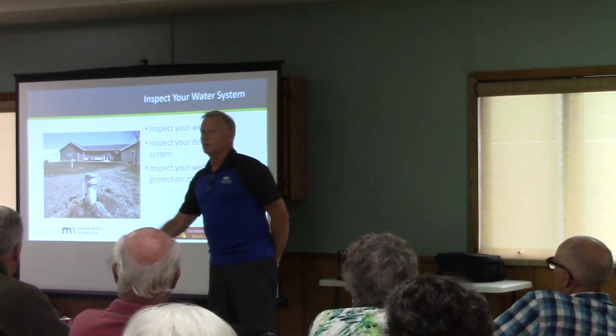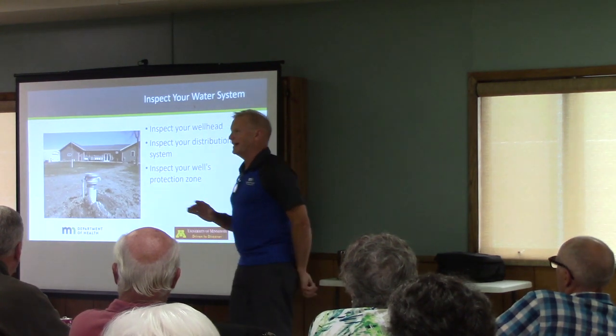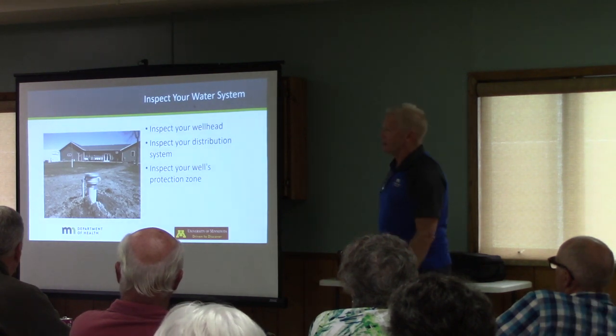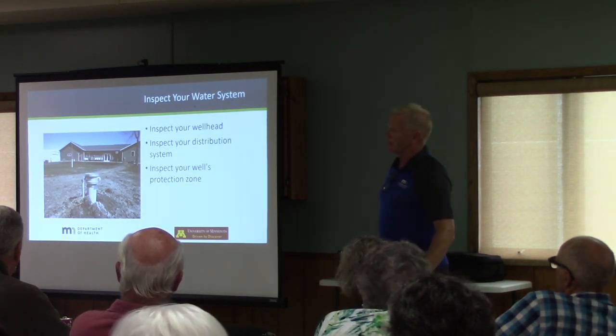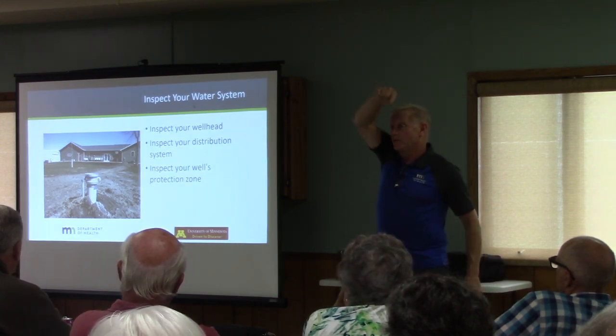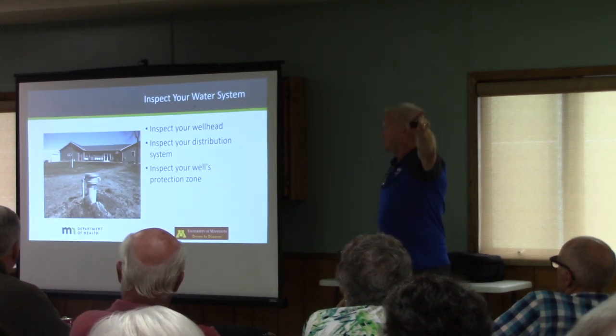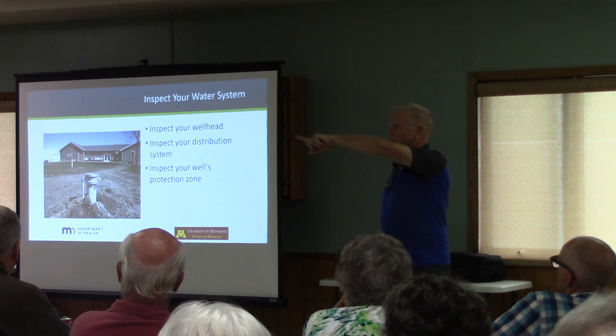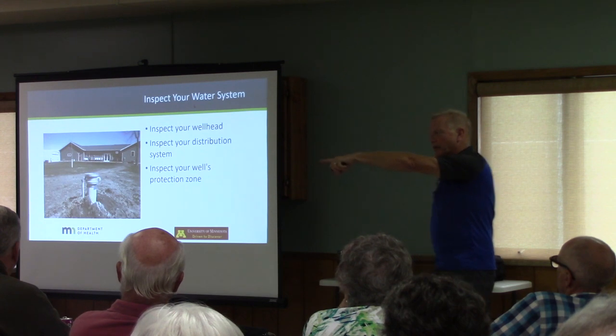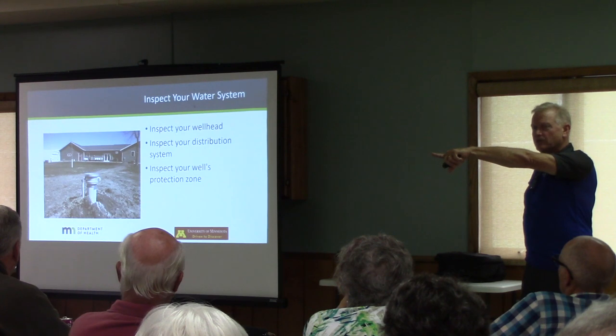Okay, now we want to look at your water system. Basic stuff, but you should look at it at least once, and then maybe you've already done it. The things you want to look at are the important components of the drinking water system that's already out in your yard, like the wellhead. There's one right out here. As you walk down the sidewalk, there's a wellhead, there's the well. The distribution system, you know, there's a hose out there that's sitting on the ground. Does that have backflow prevention on it?